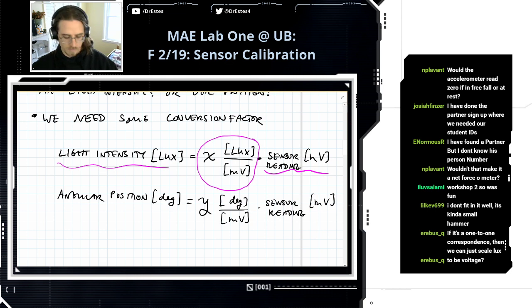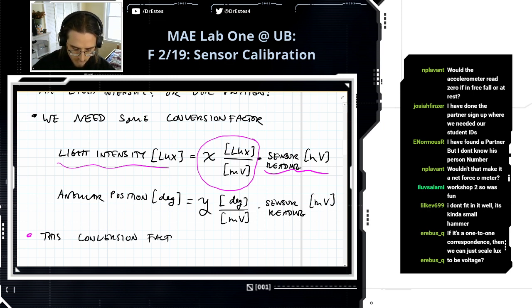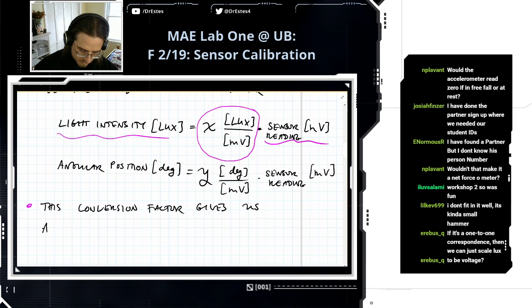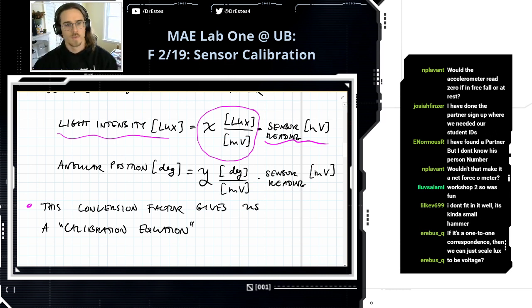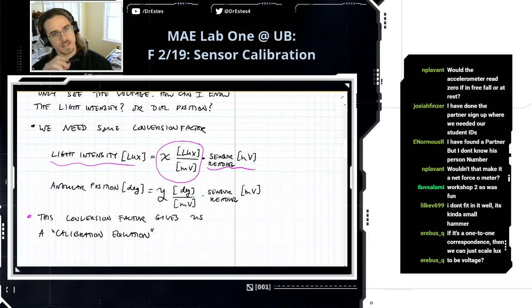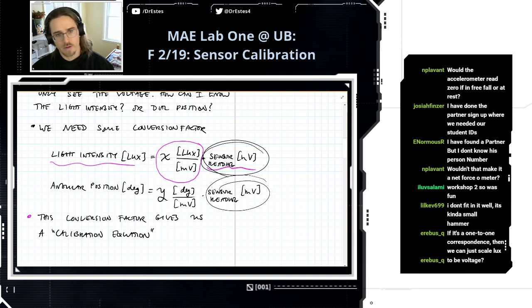Okay, so this conversion factor gives us what we call a calibration equation. A calibration equation is just a way to connect the quantities on either side of the transducer—how can I get a sensor reading in voltage and interpret what the physical quantity that was coming in might be?